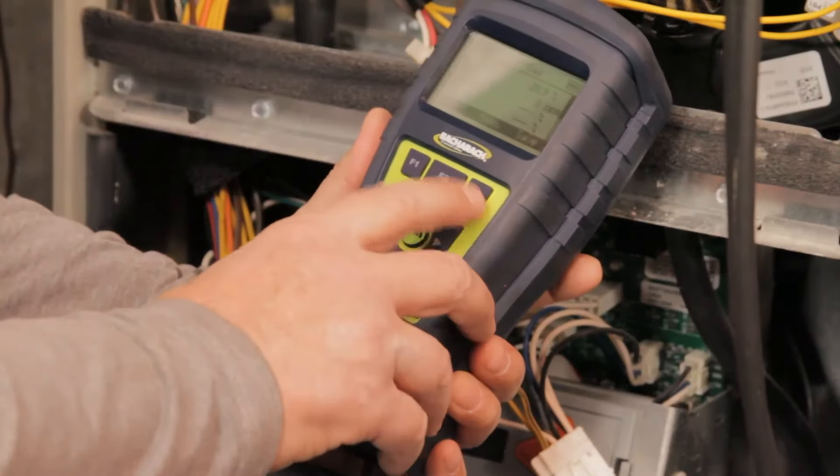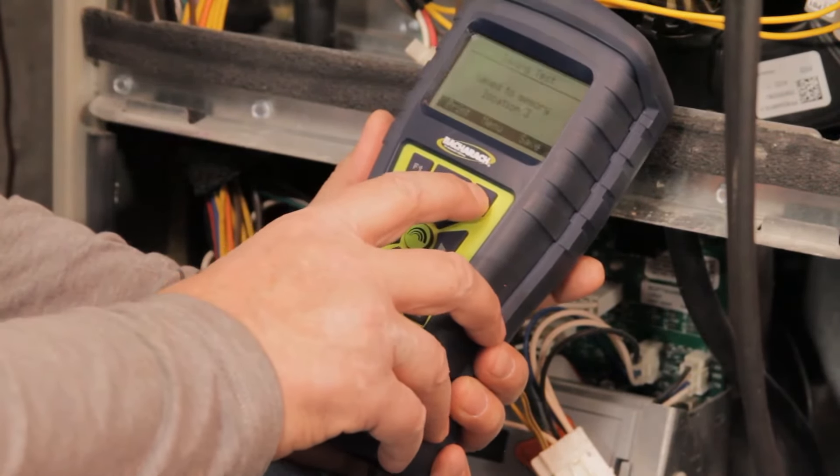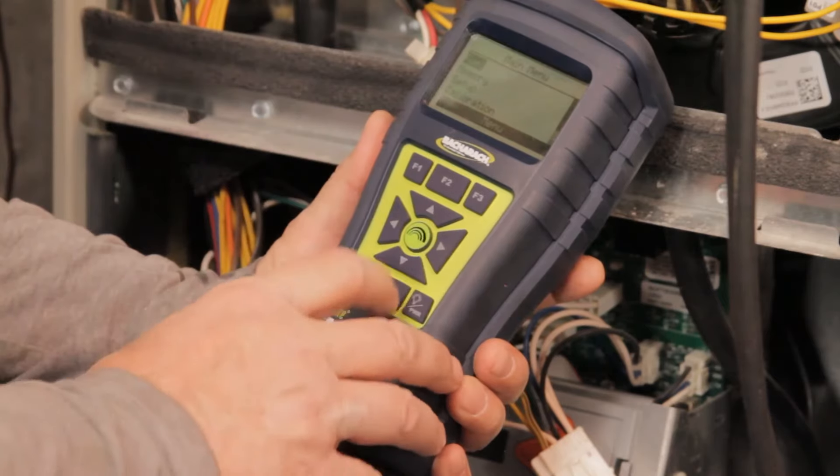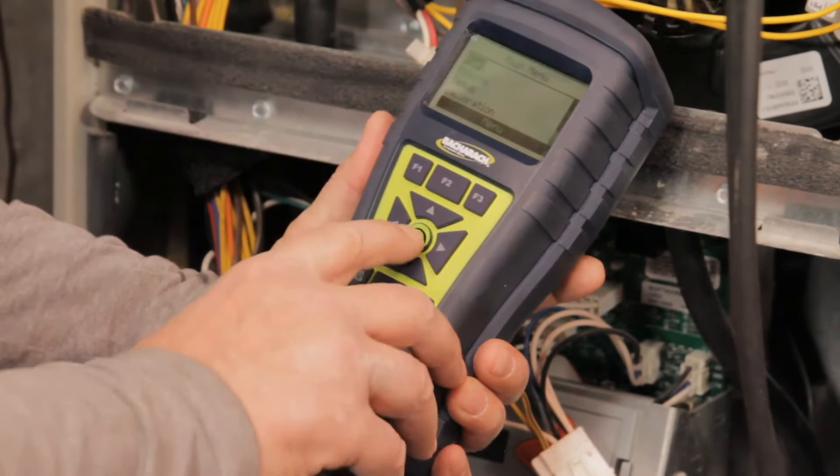Next, we verify that CO levels are within range. Carbon monoxide is an odorless, colorless, poisonous gas that is a natural and common product of combustion of all kinds. It is crucial for safety to guarantee levels are within range.